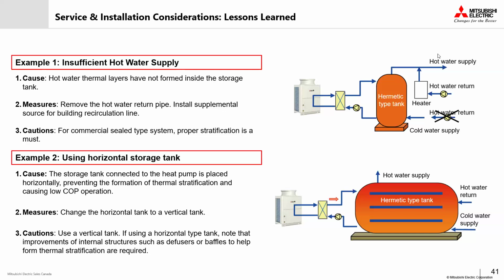And what we'll see is that hot and cold water get mixed together, especially due to how the recirculation lines might be connected to our, I guess, hot water storage or our plant. When that hot and cold water gets mixed together, it can disrupt the thermal layering that's essential for efficient operation. So if that recirculation is returned too high or in the wrong place, it can blend the warm water with the hot supply, and it makes it that much harder for the system to maintain the right temperatures. So just something to keep in mind. It is absolutely crucial how these storage tanks are configured and how our domestic cold water supply and hot water supply out into the building are connected to these tanks.